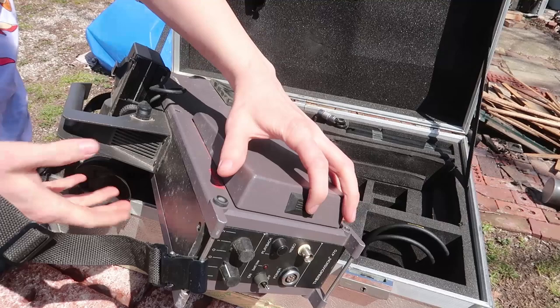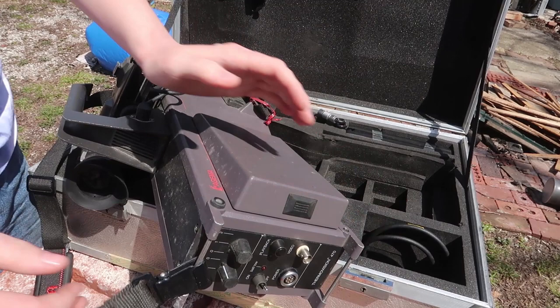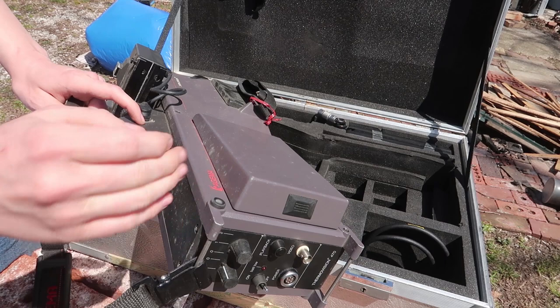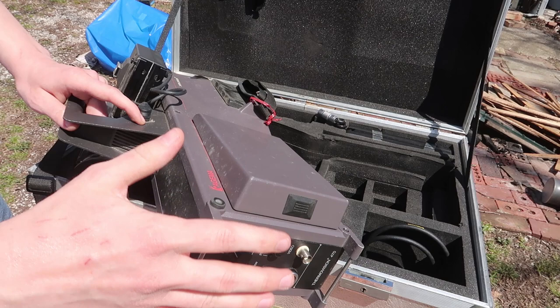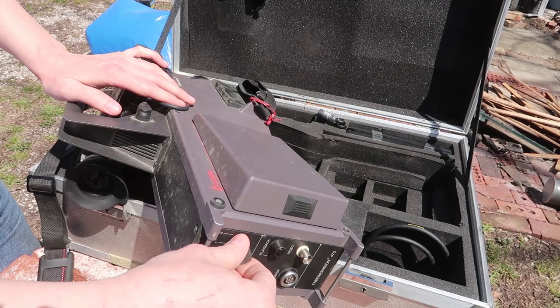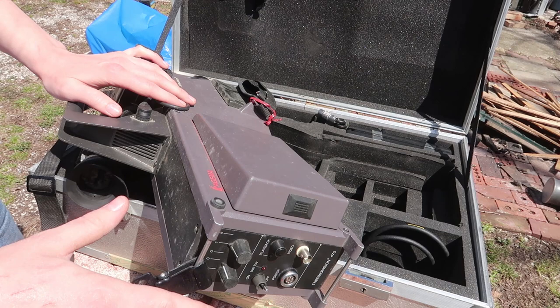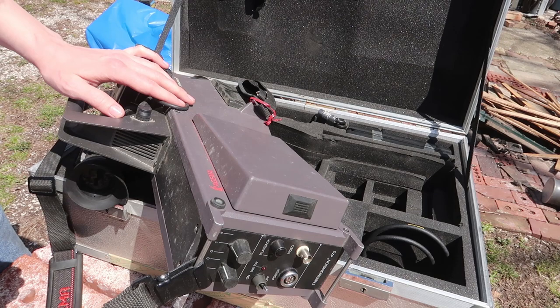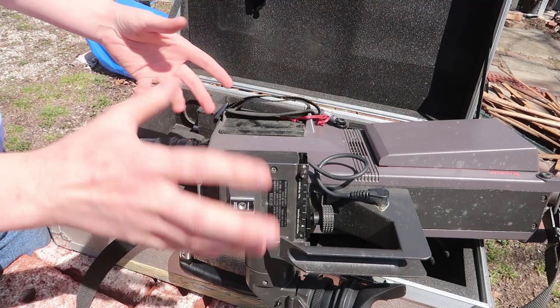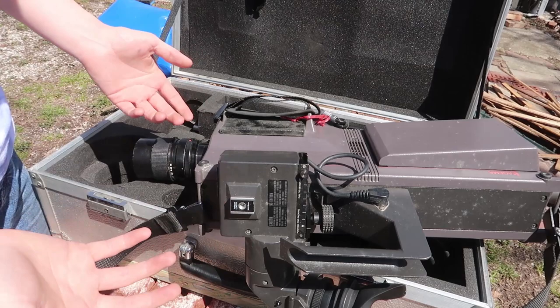So it saves to floppy disks — a 3.5 inch floppy drive. You have multiple filters. This is actually a high quality thermography camera and it can do a few things better than any of my other thermal cameras. Depending on which filter you select, you can go up to almost the melting point of iron. I believe it goes up to 1500 degrees Celsius for the second filter, and the third one might be even higher. My other camera, my thermap, only goes up to about 500 degrees Celsius and at that point it starts getting unstable.